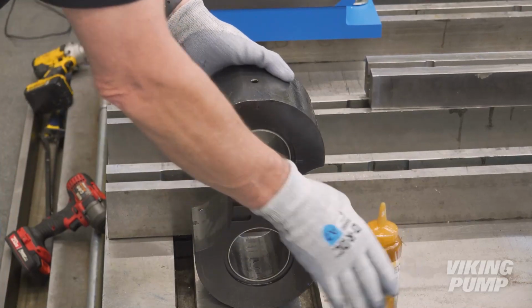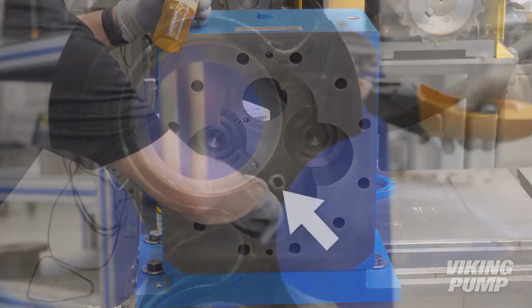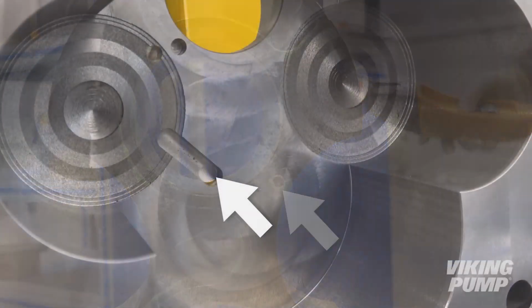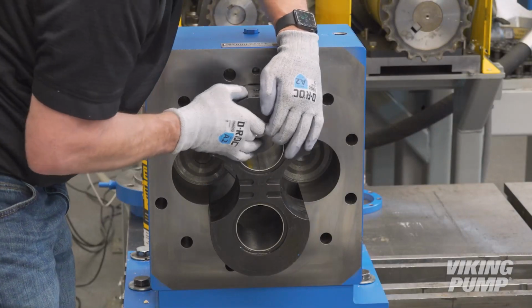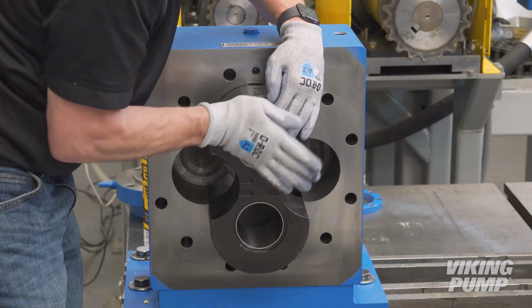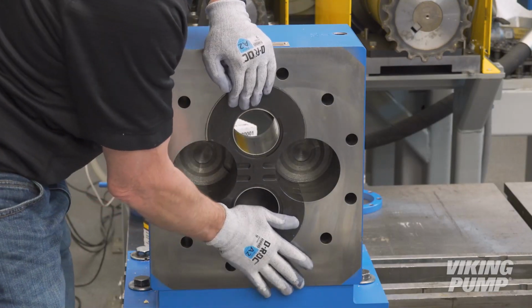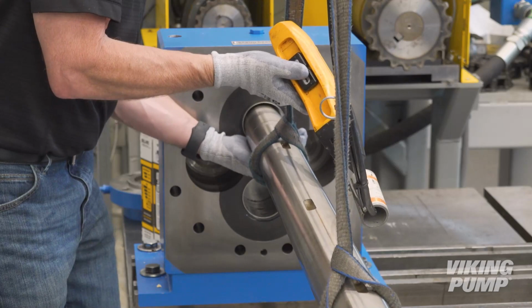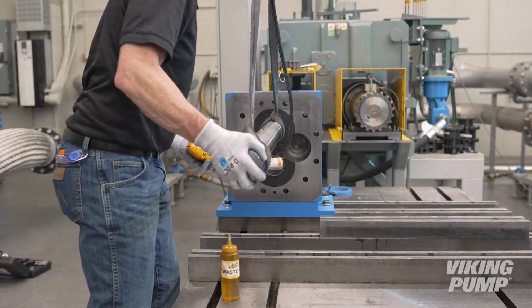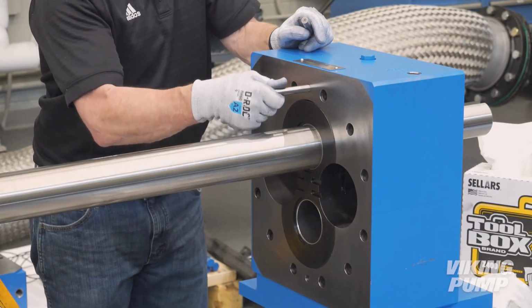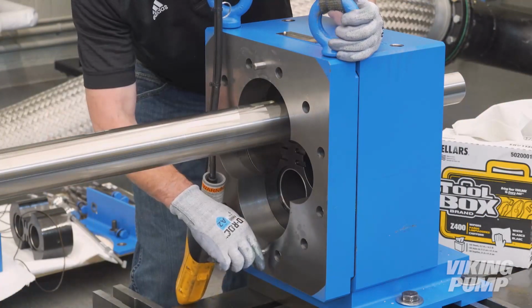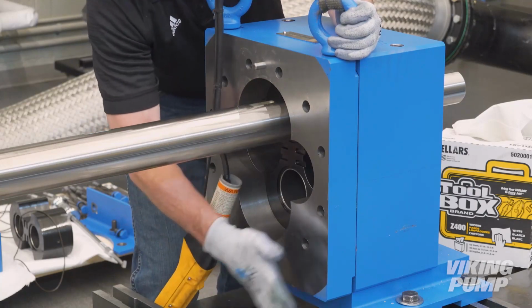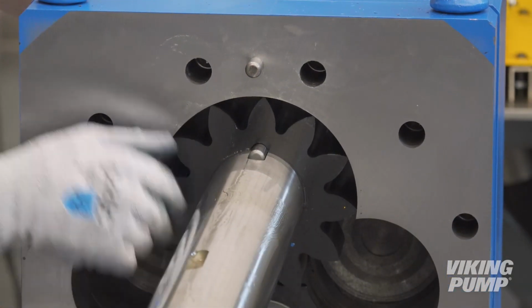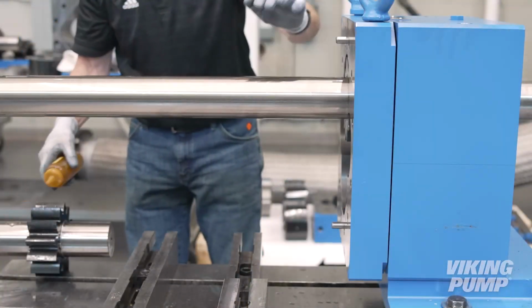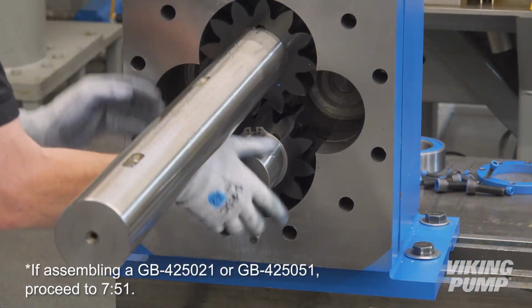Apply light oil to the bushing block and bracket bores. When installing, make sure to line up the bushing block pin with the groove in the bracket. It may be necessary to use a soft-headed hammer to gently tap the bushing block into place. Be careful not to damage the faces of the bushing block. Install the shaft into the bracket. Install the alignment pins and casing. Install the drive pin and coat the driver shaft with light oil. Install the driver gear. Apply light oil to the driven gear and driven shaft assembly and install.